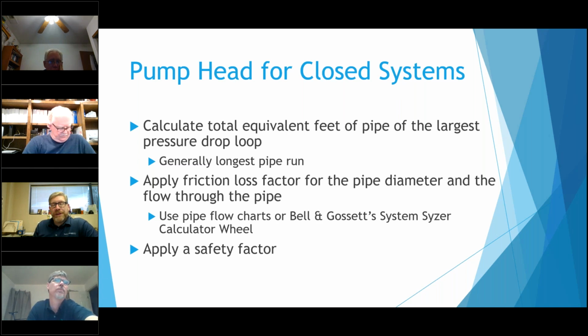After that's all been added, you want a safety factor applied to the whole foot of drop that you need to overcome. Typically on smaller systems you're going to use a larger one, just because it still doesn't affect it too much. Some of the smaller systems only have like 15 or 20 feet of pressure drop in it, so to put 50% on top of it isn't really that much.